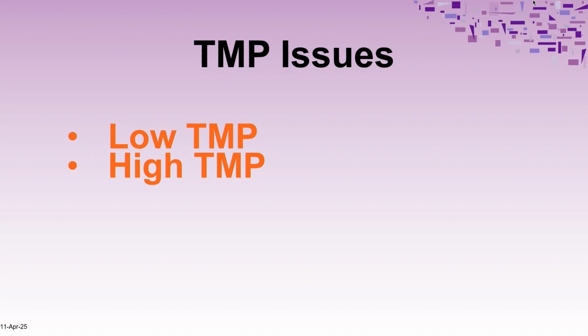Yeah. And high TMP obviously is kinked tubing before the dialyzer, because now the machine is pulling and there's no more fluid coming in. So what happens to the negative pressure? It increases. And then clotting in the arterial header has the same thing.